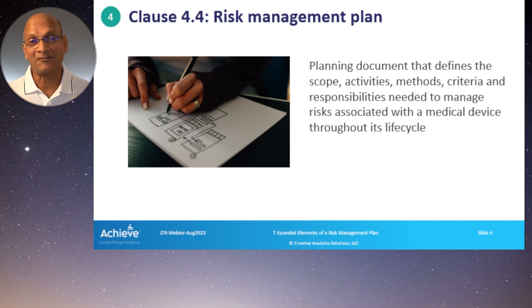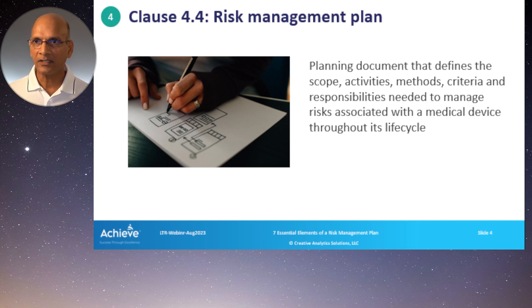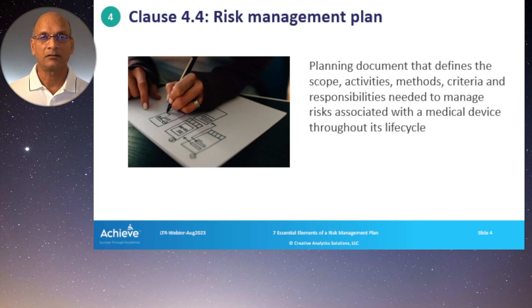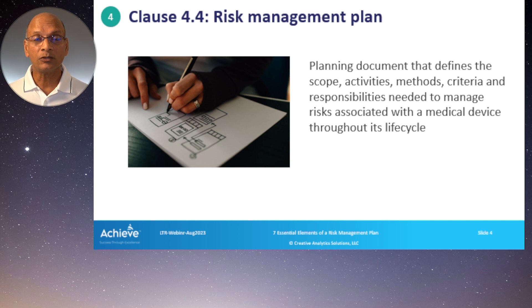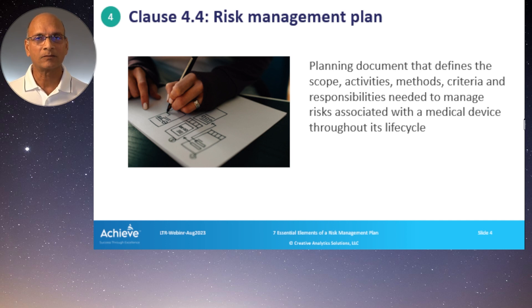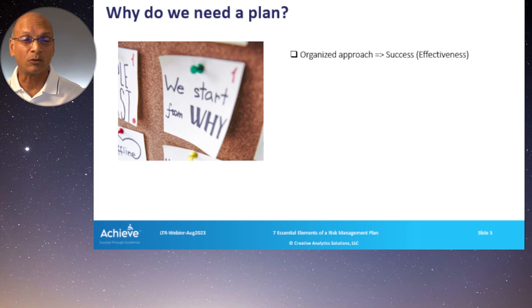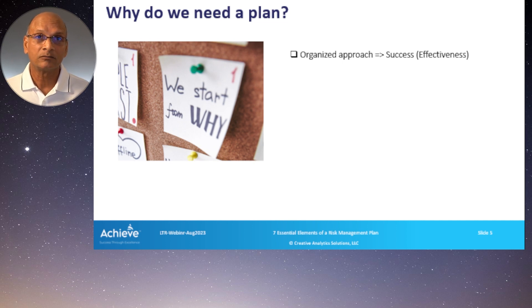So the risk management plan — what is it and why do we care? Everything has to begin with planning. It is a planning document that defines the scope, activities, methods, criteria, and responsibilities needed to manage all the risks associated with a medical device throughout its life cycle. That's a key point — the plan is not one and done. The plan has to be updated throughout the product life cycle, and that's one place where we struggle a lot. I'm going to present an optional eighth element that I include in my templates, which is not required by 14971, but that optional element will actually help you manage the risk management plan.